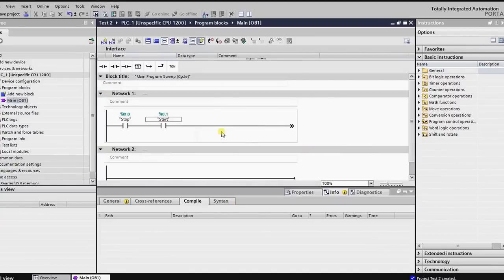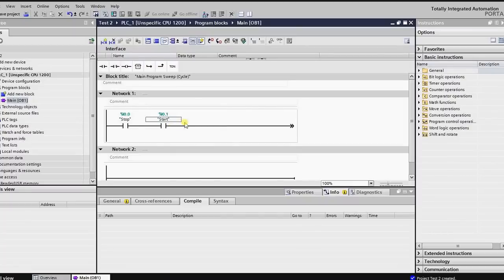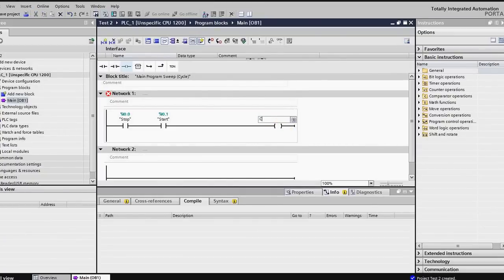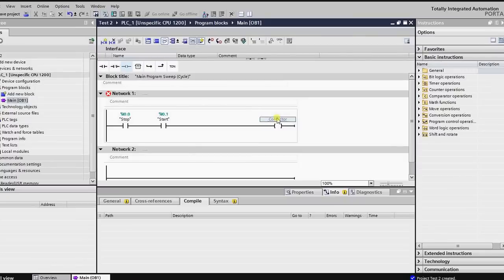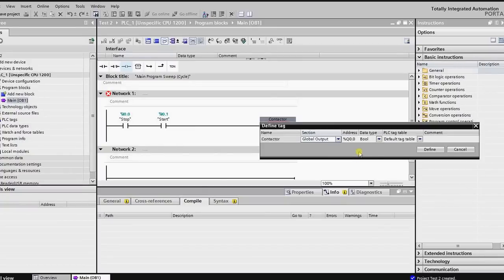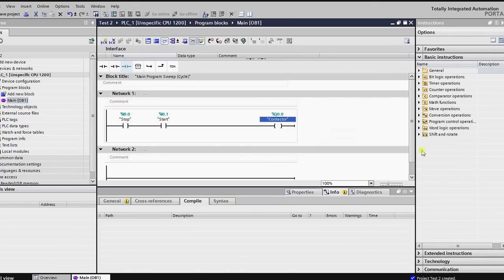It'll automatically change it to I0.1. Now, if you want to do that different, you can just change the 0.1 at the end to anything you want it to be on your PLC. It's up to you. It's just easy. I find it's easier to use what it tells you, and then we'll put an output. So this one up here is the symbol for an output, and what you want to do is, we'll name this Contactor, because that's usually what you use for PLCs, and then we'll define this tag. This time we're going to click Output, and so now you can see it's a Q instead of an I, and Q is the pretty much universal symbol for output, and so as you can see, it's been defined.